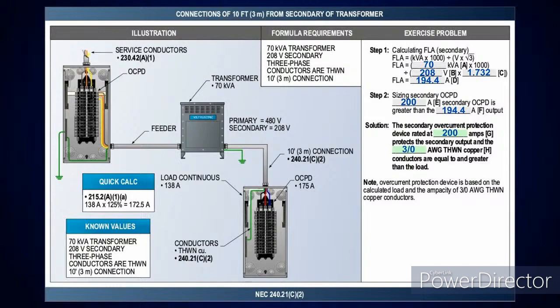Now, this is where we get in. They actually came in, I forget what cycle it was, and a lot of people used to say, oh, just tap the secondary side of that transformer. Well, that didn't make it a tap. Those are actually connections from the secondary of the transformer. So they came in and they rewrote this article, specifically 240.21, and that's why we have 240.21(B) and we have (C) now. And this one here is where we got connections from the secondary of the transformer. Now, this particular one, we're looking at (C)(2), and this is connections for 10 foot here.